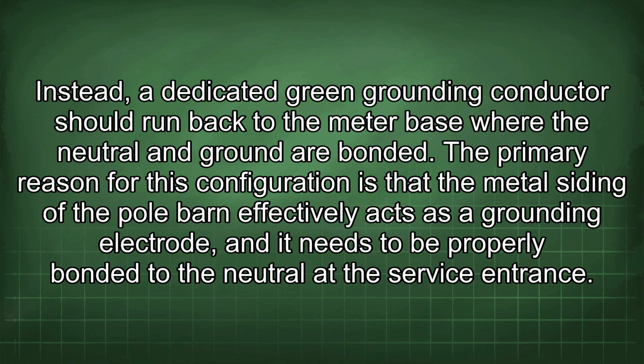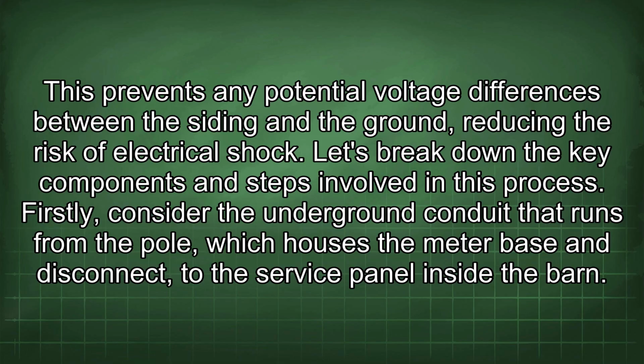The primary reason for this configuration is that the metal siding of the pole barn effectively acts as a grounding electrode, and it needs to be properly bonded to the neutral at the service entrance. This prevents any potential voltage differences between the siding and the ground, reducing the risk of electrical shock. Let's break down the key components and steps involved in this process.